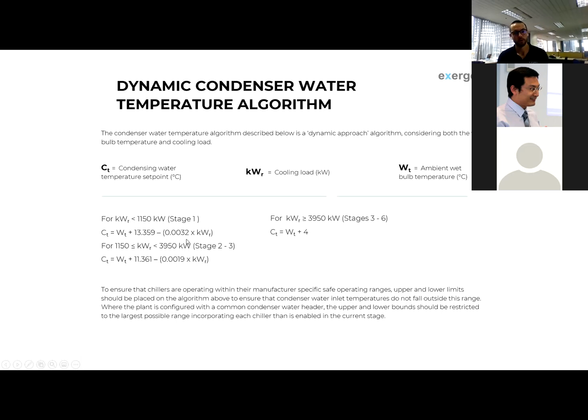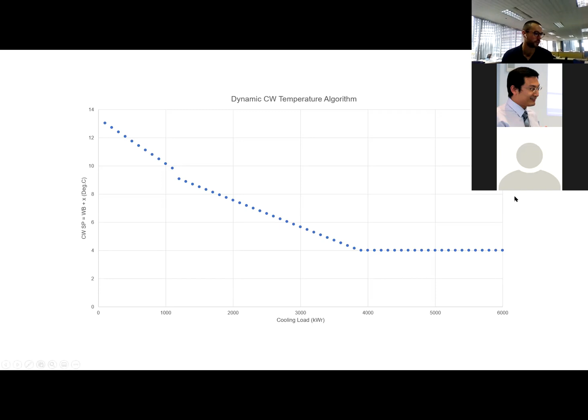Again, on the x-axis is cooling load, and on the y-axis here we've got wet bulb plus X, which is what this turns out to be. So you can see, rather than starting at very, very low condenser water temperatures and trying to extract more efficiency out of a chiller that's not doing that much work, the model suggested that it's more efficient to float that condenser water temperature higher and then bring it down as the chillers increase in load, and it's worthwhile running those fans to extract that additional efficiency from the chillers.